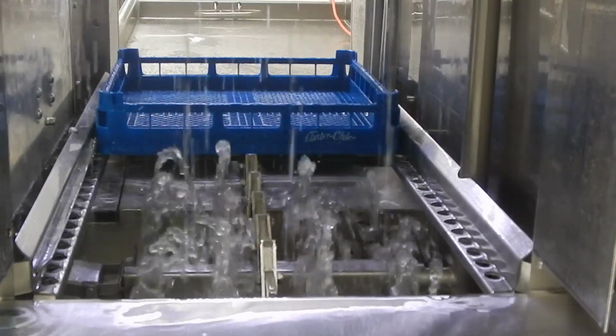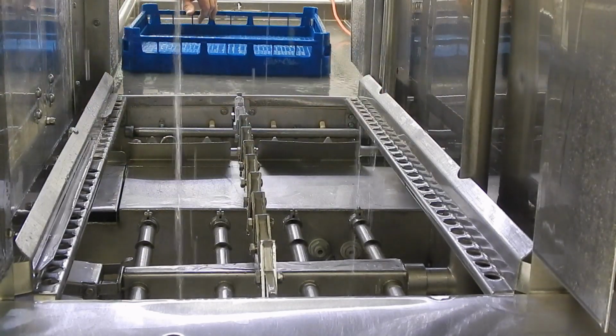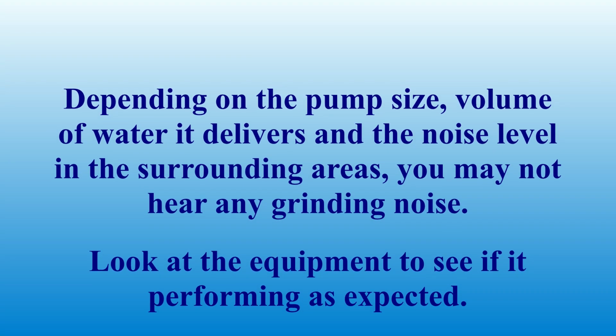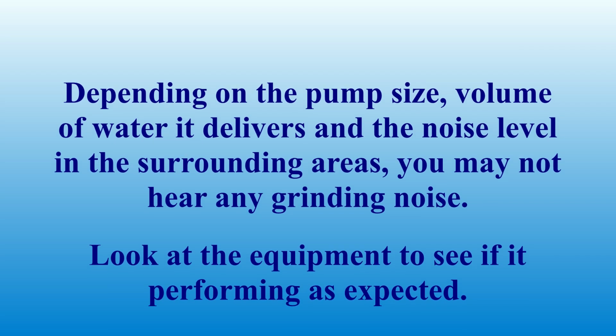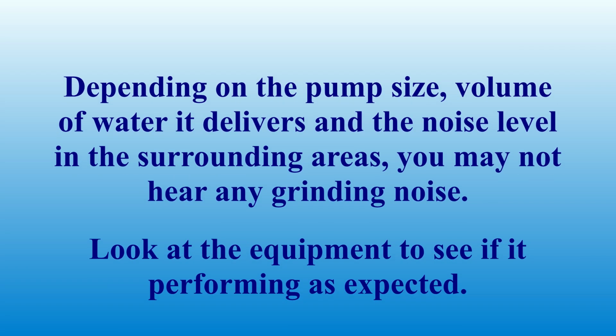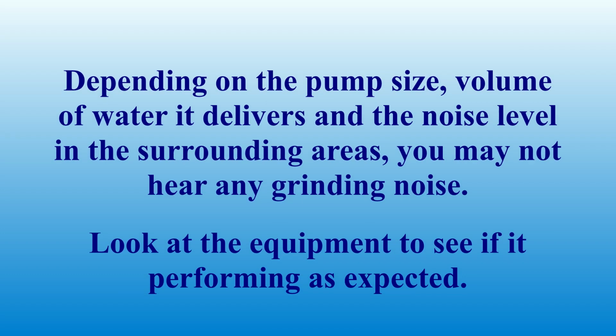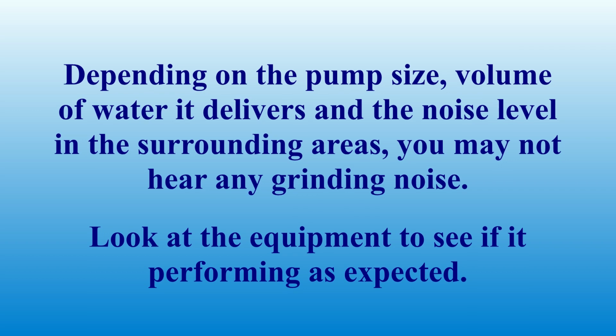Again, a couple of things that could be causing this. One could be bad procedures on the customer's part. But generally, when you hear the grinding noise, it's because the motor is actually running backwards. So remember, reversing any two of the lines will reverse the polarity of a three-phase motor. Depending on the pump size, volume of water it delivers, and the noise level in the surrounding areas, you may not always hear the grinding noise. Look at the equipment to see if it is performing as expected.